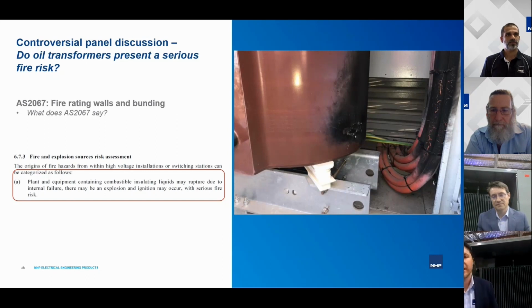So here's a photo taken from a site where there was an internal fault within a cast resin transformer, and as you can see, there's a hole that's been punched through the material. Looks like a lot of heat has been generated there. A lot of blackening, carbon and soot and other things there.